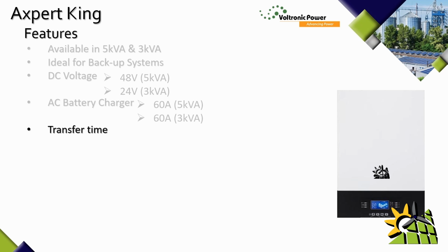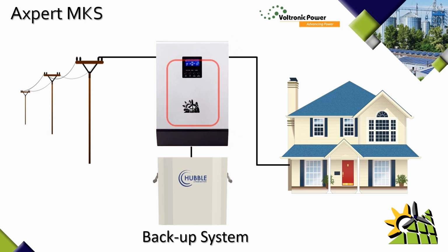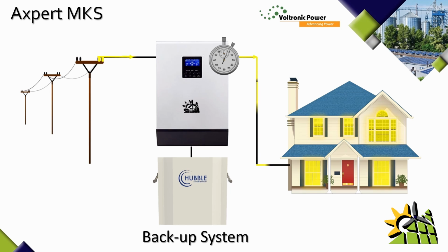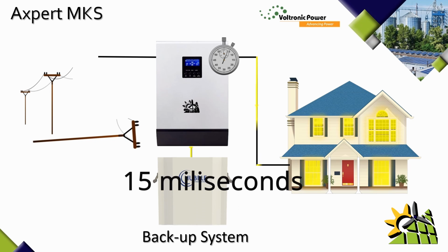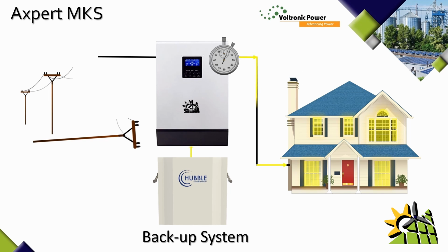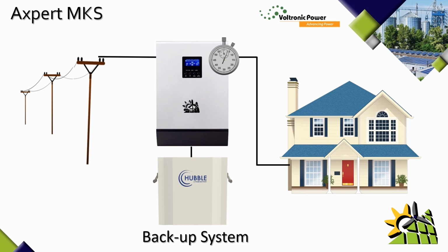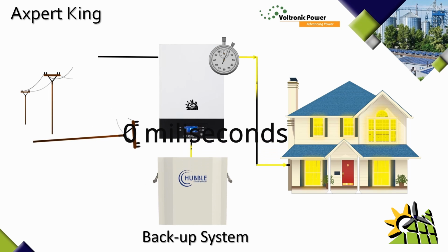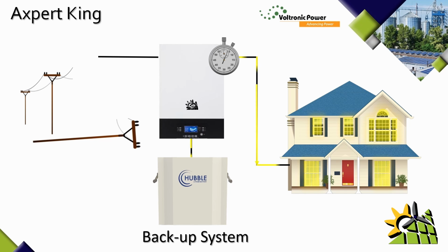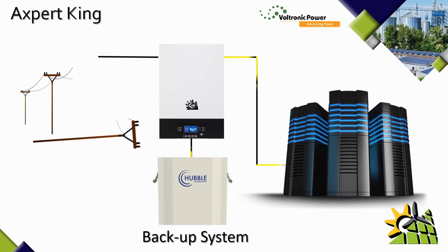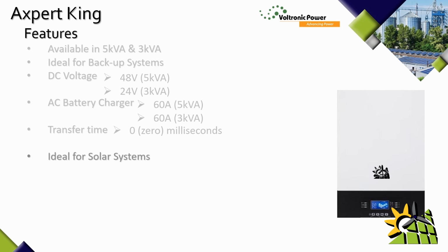The transfer time on this inverter is 0 milliseconds. Now, let me explain to you what that means. Let's look at a normal MKS inverter. Now, this inverter is very similar to the Axpert King. However, in the event of a power failure, the inverter will take 15 milliseconds to switch over from grid mode to battery mode. Now, under normal circumstances, this will be fine. However, the Axpert King will have a 0 transfer time in the event of a power failure. So in other words, if the grid falls away, there would be no delay in grid mode and battery mode. The inverter will switch over immediately with a 0 millisecond transfer time. Now, this is very important when you have sensitive IT equipment such as a server that doesn't like that 15 millisecond transfer time.